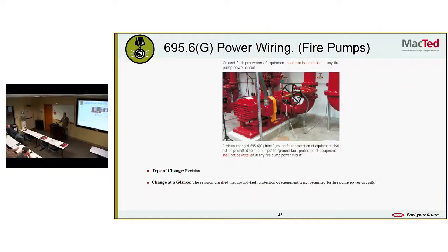All right, fire pumps. This ought to get some blood flowing, huh? A little excitement. Something big. The revision clarified that ground fault protection of equipment is not permitted for fire pump power circuits. You wonder why. Put it on everything, but something you rely on. At least they recognize that they're a nuisance, some of them. They had a place burned down. Yeah, I would imagine. They want them to run no matter what.